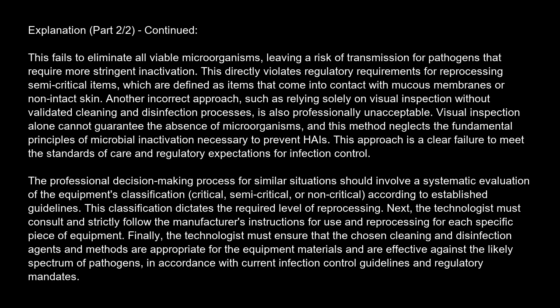This directly violates regulatory requirements for reprocessing semi-critical items, which are defined as items that come into contact with mucous membranes or non-intact skin. Another incorrect approach, such as relying solely on visual inspection without validated cleaning and disinfection processes, is also professionally unacceptable. Visual inspection alone cannot guarantee the absence of microorganisms, and this method neglects the fundamental principles of microbial inactivation necessary to prevent HAIs. This approach is a clear failure to meet the standards of care and regulatory expectations for infection control.